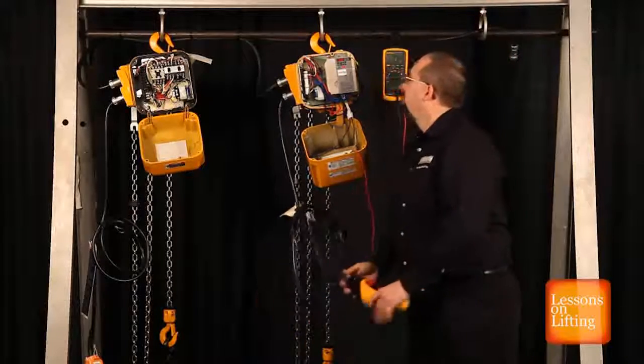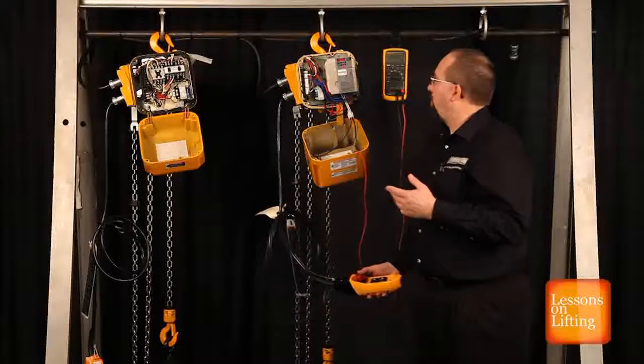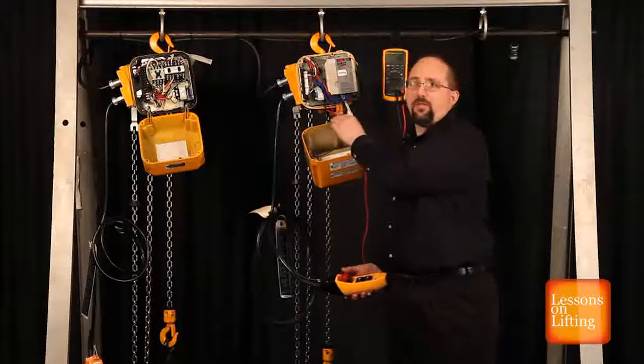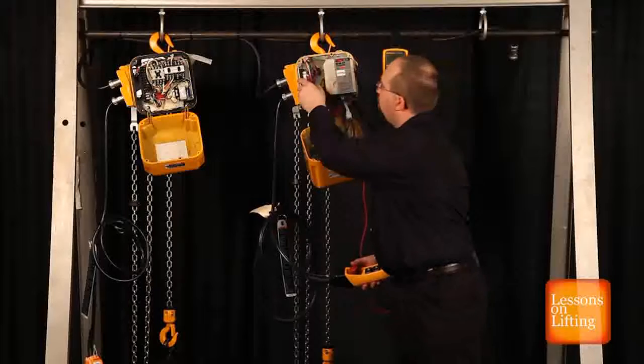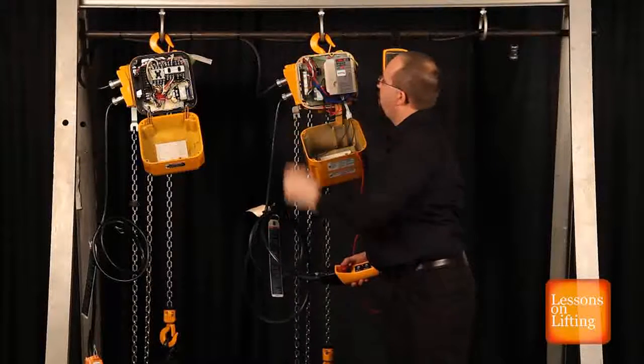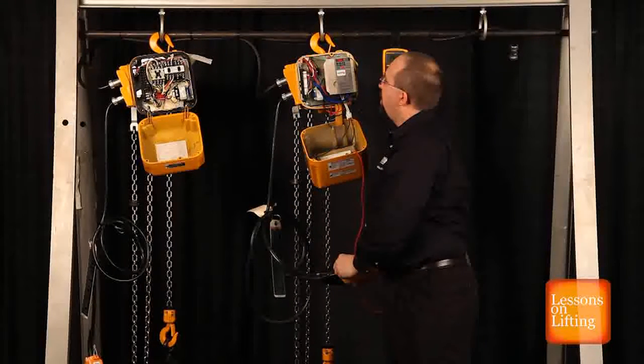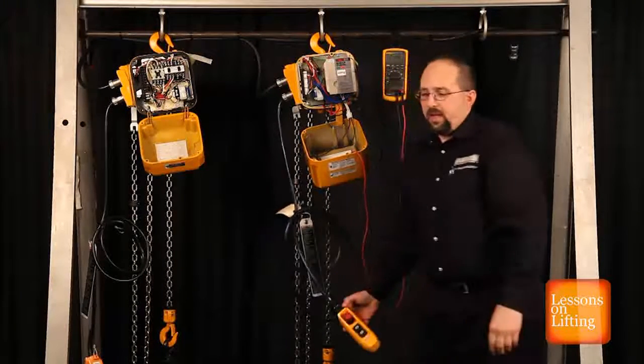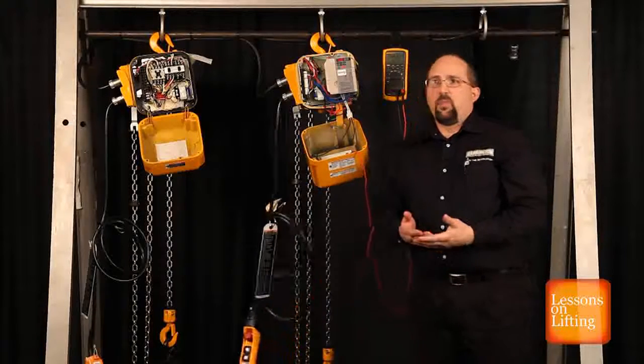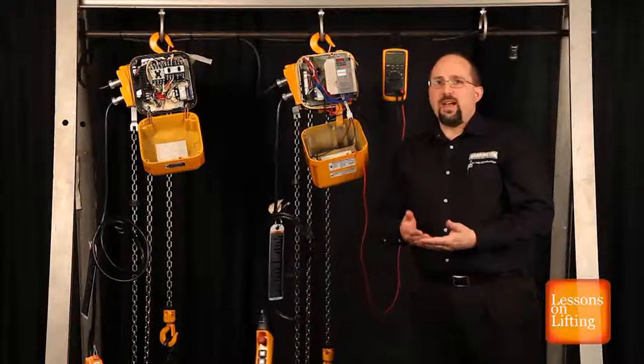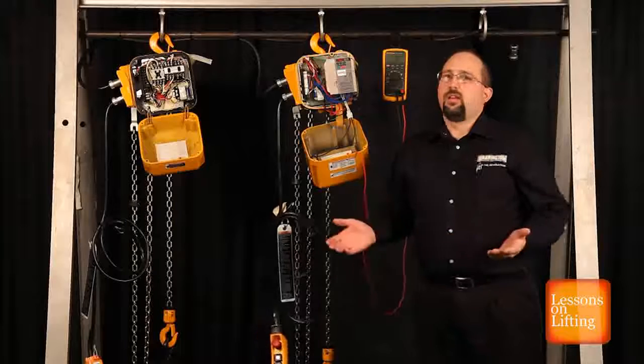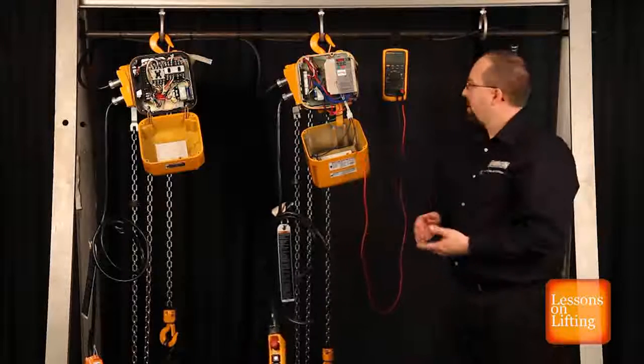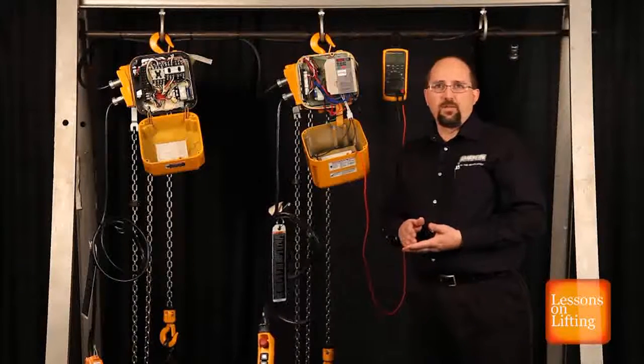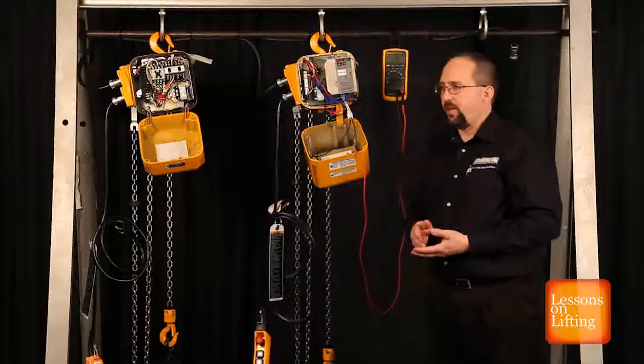RY11, it's the center relay on the interface board. And what you're going to want to do is just look in there, and as you push and release the E-stop button, you should hear it click, and you should see the contact points open and close. If those contact points are not opening and closing, and we did have control voltage, then you need an interface board. Okay? It's that simple. The relay's not serviceable, it's not replaceable, you need an interface board.